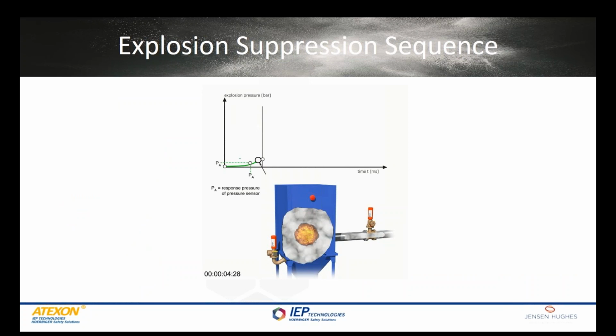Here is a quick animation showing an explosion within a dust collector. We'll see an ignition source, the pressure that travels up, detected by the detector. Very, very quickly, flame is ejected, powder is ejected to absorb the heat from the flame. And in conjunction with that, you'll see an extinguisher on the inlet duct, and that extinguisher discharges to create a chemical barrier to stop any flame going back upstream.